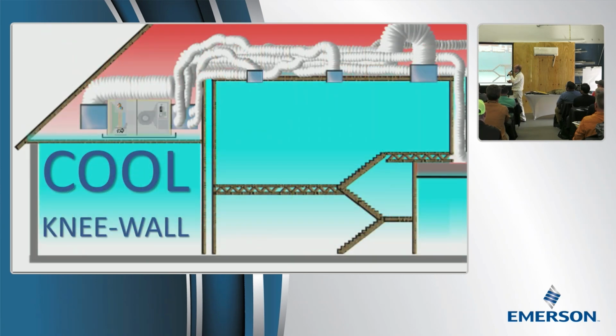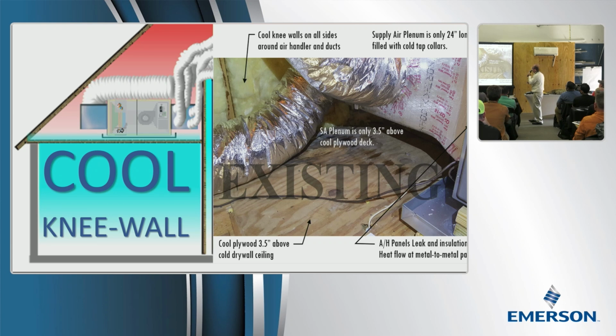The cool knee wall is a place where you can see all kinds of things happening, because you don't have your typical radiant heat source since you're right up against this cold knee wall. So everything's different. Usually it looks something like this: here's the cold knee wall, here's the duct laying on the cold plywood, and the air handler and everything's dripping.